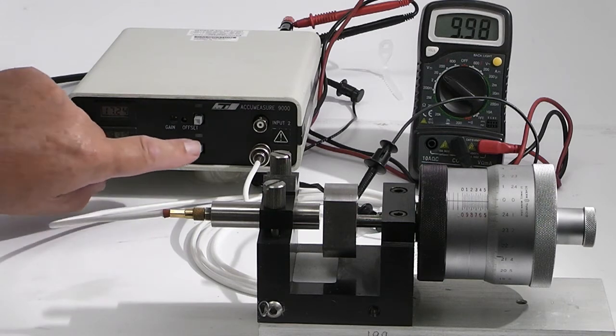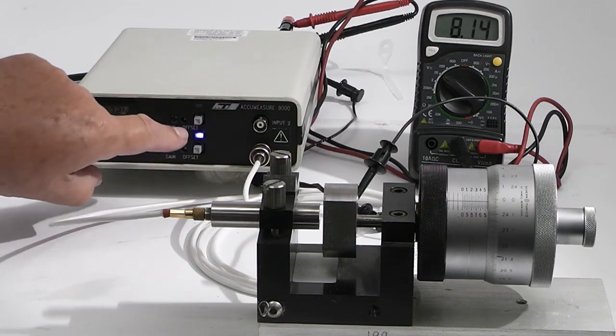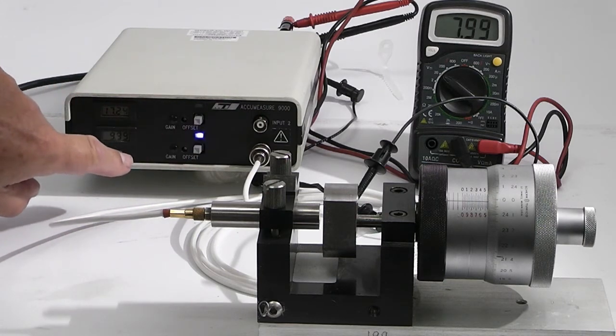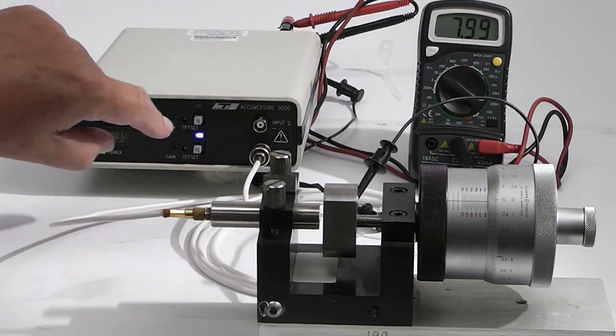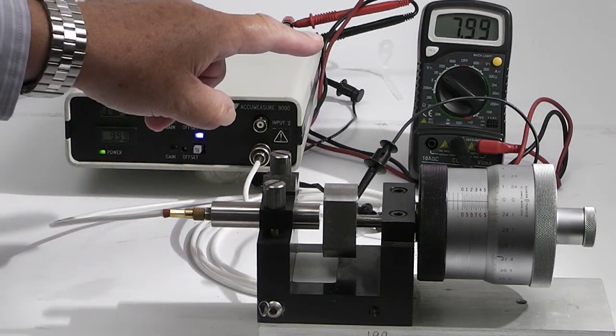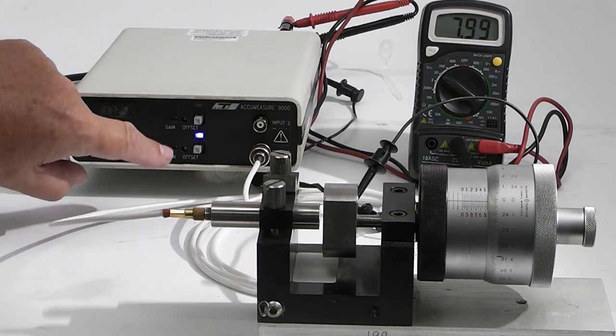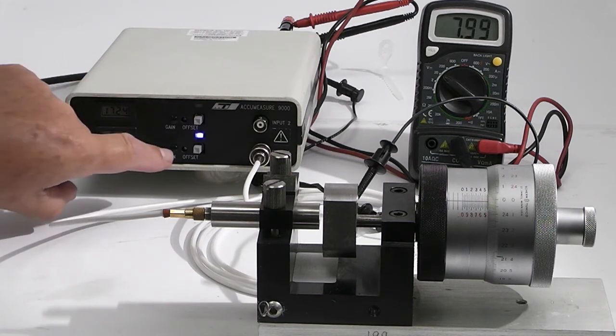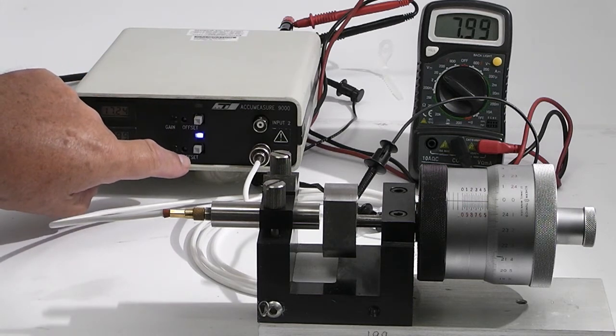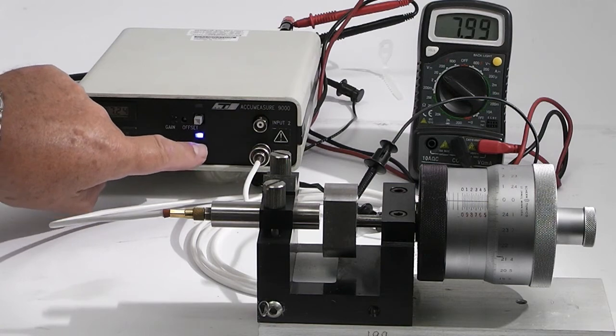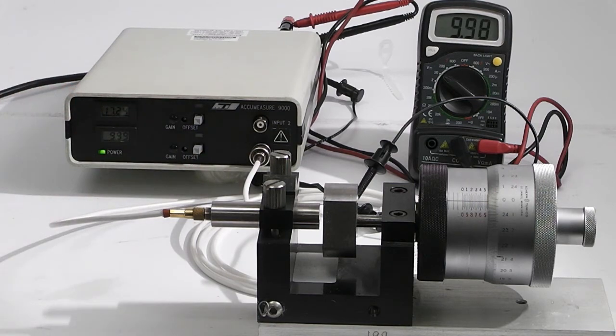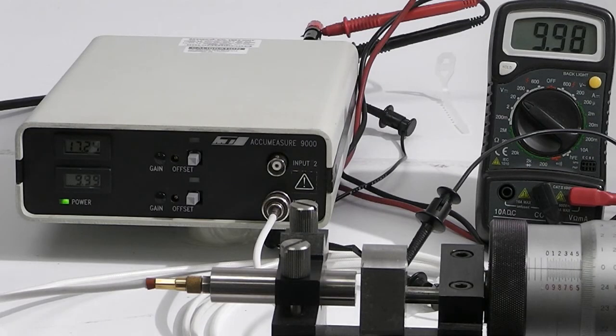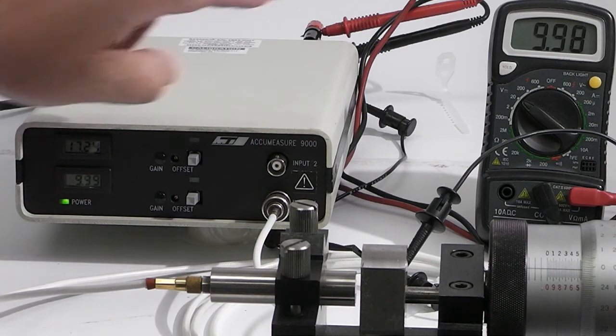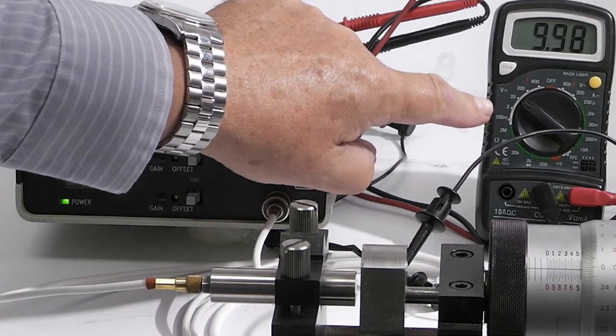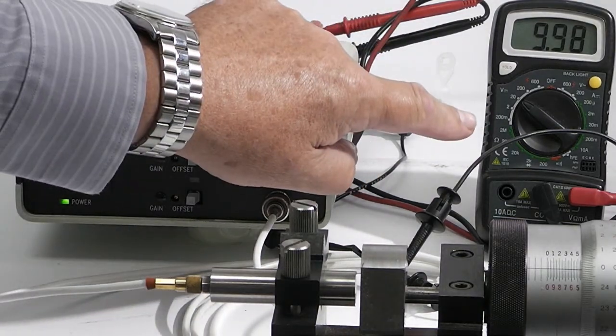The front panel offset button can be depressed, indicating with the blue LED on, and this will then adjust our output. And here it goes from 10 volts to 8 volts, or any other value can be selected by turning the offset potentiometer in the front of the unit. The voltage reading can be either read on the front panel digital display of the amplifier or in a separate digital voltmeter connected to the rear terminals for channel 1.